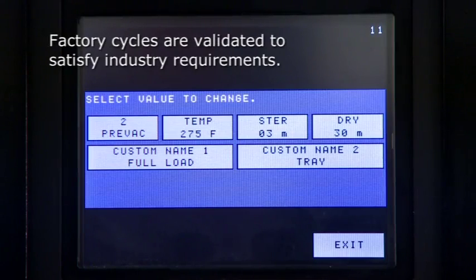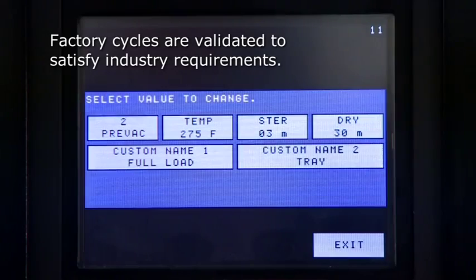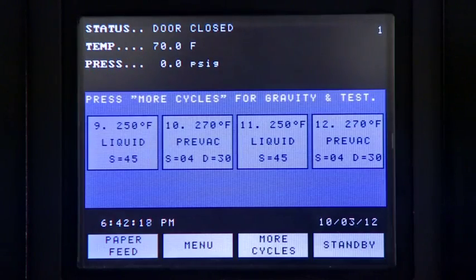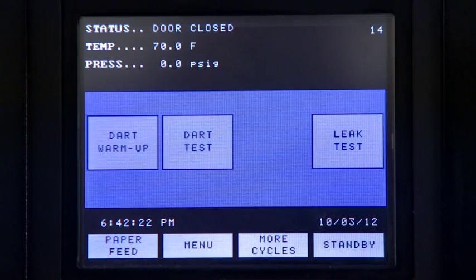It is important to note that settings in factory cycles have been validated to satisfy the appropriate industry requirements. If cycle sterilization times, dry times, and temperatures other than those set by factory settings are required, it is the responsibility of the healthcare facility to consult and follow the device manufacturer's written instructions. Dart and leak test cycle parameters are fixed. The buttons for these cycles do not display values for exposure temperature, exposure time, or drying time.